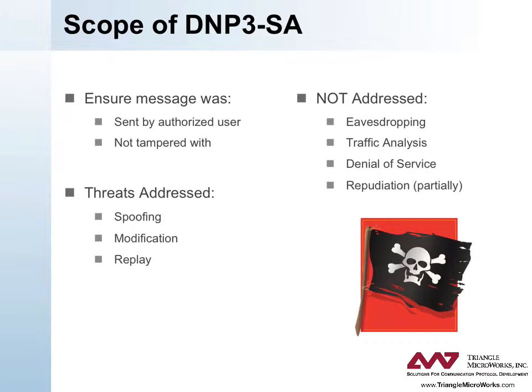It's also important to understand what DNP3 Secure Authentication does not attempt to do. The mechanism does not encrypt the message. This may surprise some people who assume that all electronic security involves scrambling the message. It was decided by the DNP3 Technical Committee, on the advice of utilities, that it was not necessary to protect the message against eavesdropping — an attacker reading what data was in the message. Encryption requires significant processing power on the part of the transmitting and receiving devices, and this cost was not considered worth the benefit, except for encrypting the keys that are downloaded to the outstation.